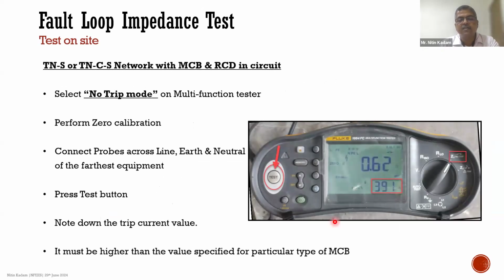Now, when you go to the TN-S network or a TN-C-S network, but in addition to MCB, the customer has also provided an RCD, in that case you cannot do the test with the high current trip mode. You have to move this knob to the no current trip mode or no trip mode. And on the multifunction tester, again perform the zero calibration for the probes. Connect the probes on the line, earth and neutral in this case on the farthest equipment. In case of elevators, it could be the variable frequency drive, which is providing the power supply to the machine or the motor of the elevator. Press the test button. Again, note down the trip current values here. And this has to be higher than the table which I was showing in the previous slides. If this is higher, then the fault loop test has passed. If it is lower, then the fault loop test has failed, and you have to work on the measures of bringing down the fault loop impedance values.